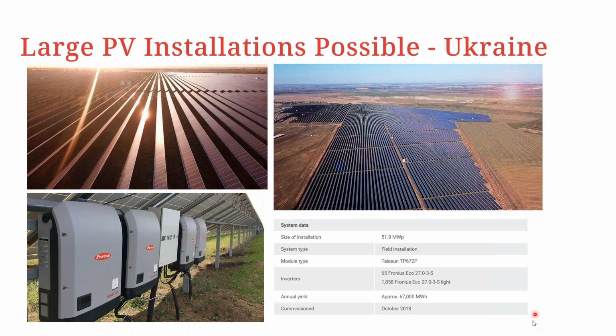So you can see that you can achieve very big installations using the Fronius Eco inverters. But of course, it requires a bit of consideration when you're deciding how you're going to interconnect all the inverters together. Because as we can see in this case, we have a few full version inverters and quite a number of light version inverters. Theoretically, as we know, we can connect up to 100 inverters per one Data Manager, but of course, that will vary from one design to the other, especially regarding the control speeds that you want for power production.